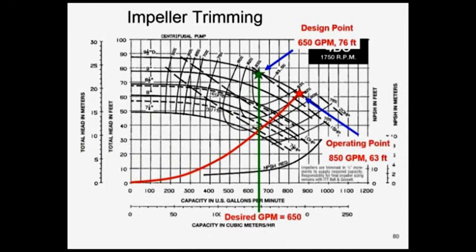We leave our throttling valve wide open. If we trim that impeller to the proper size, what happens cost-wise? Well, the little orange star is where we need to be. By the way, I can do the same thing with a variable speed drive. I can take it to that point and trim the impeller electrically by just slowing the speed down. But if I trimmed it, it'd be to 7.6 inches versus original 9.5. So if I pull the pump impeller out of the pump and trimmed it to 7.6 or slow it down, that's where I'm going to need to be.